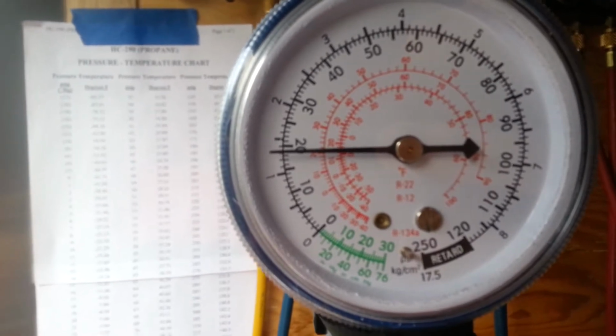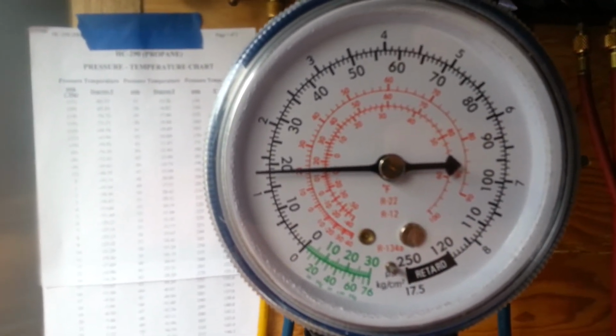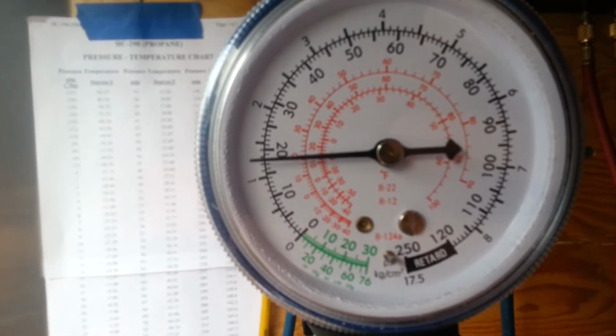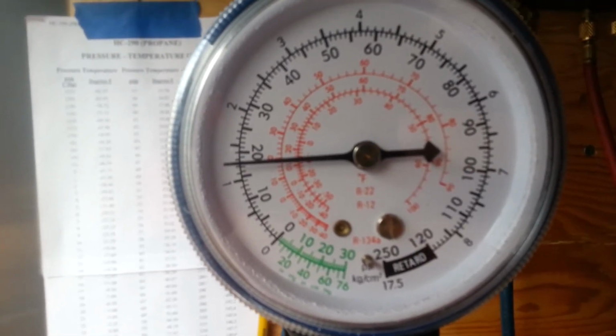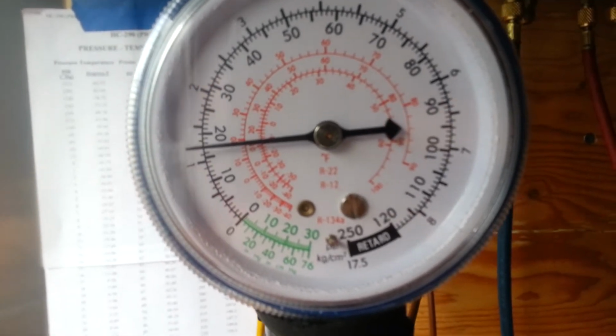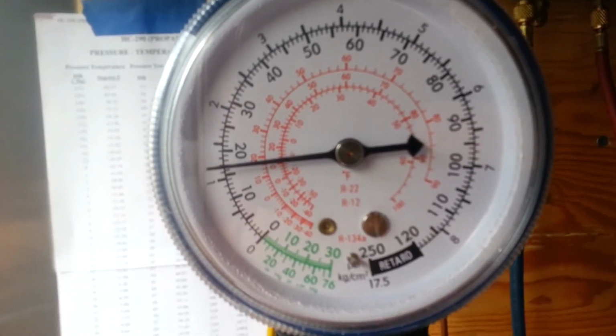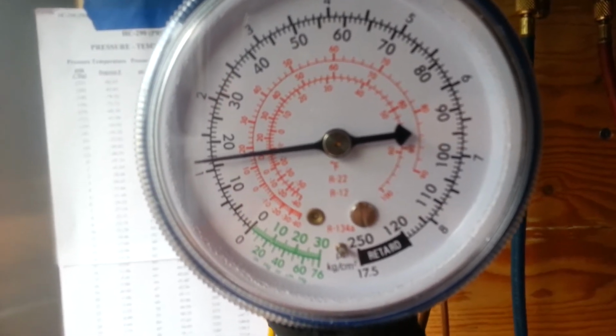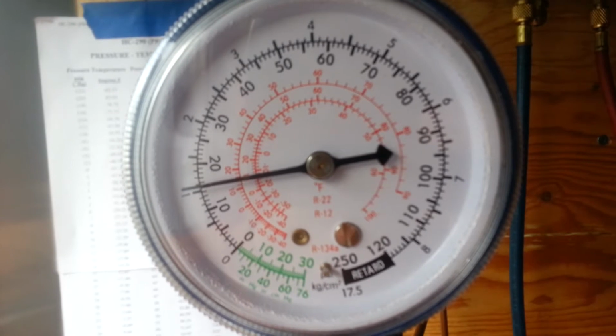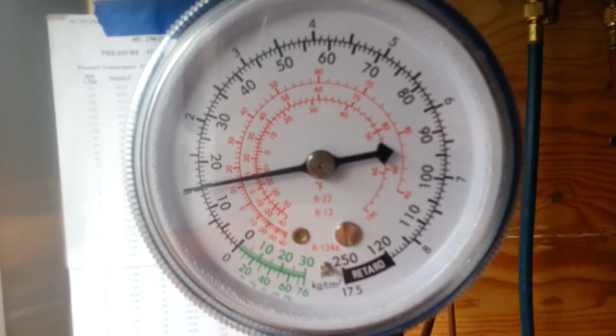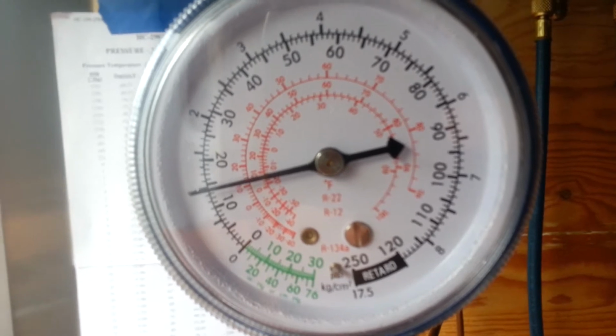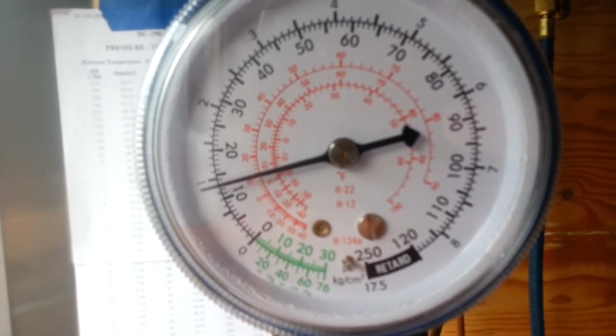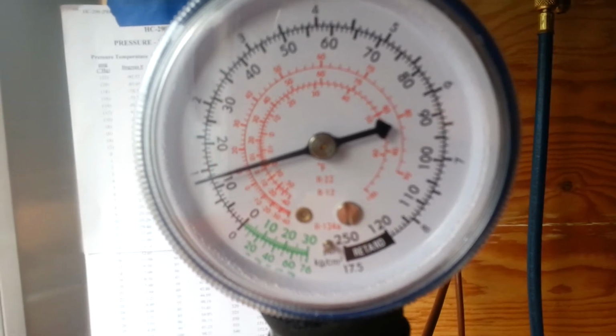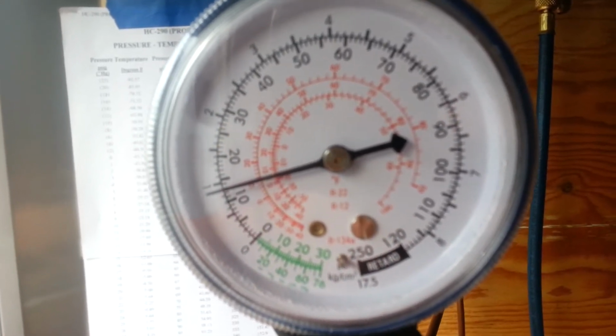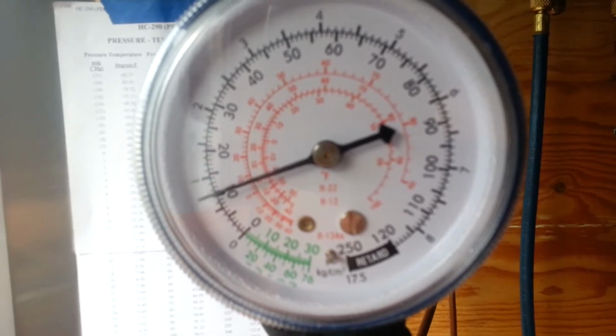I can, say for instance, if I crank it shut a little bit, see the pressure start to drop. Crank it a little more so it goes a little faster. So what's happening is the compressor is actually drawing off vapor just as it was before, but less refrigerant is being admitted from the high side, so the pressure drops. So I have to tweak or play with it a little bit. It's very, very sensitive. Needle valve is a bit of a misnomer. It really doesn't have a needle in it. Needle control. It's a flat piece of machined steel. Whoops.